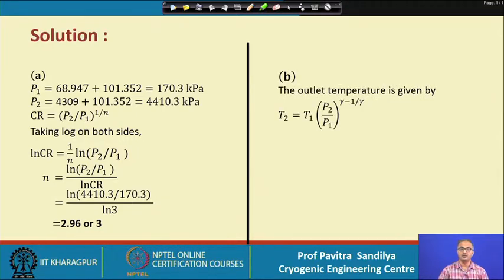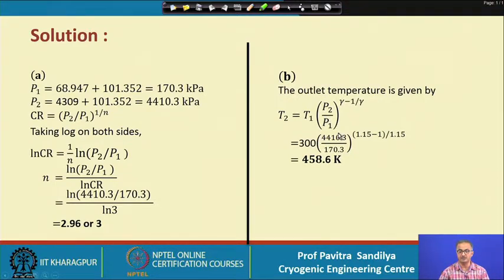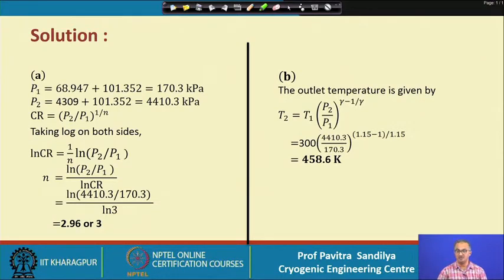To understand why multiple stages are needed instead of a single stage, we calculate the temperature rise for single-stage compression. Using the total compression ratio with the inlet temperature and the initial and final pressures, we find that there would be about a 160 Kelvin rise in temperature with a single stage. This is the reason why multiple stages are recommended.